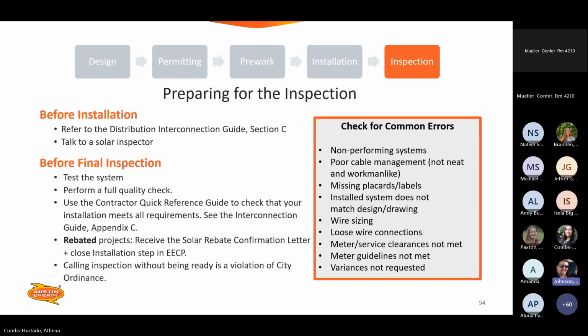Wire sizing, there are times we see too small of wires. We do have the interconnection guide, the DIG, that does tell us what size wires minimum, and same thing with the design criteria manual, what size wires minimum through any meter enclosure, what size grounding conductor through any enclosure. Loose wire connections or wires not being fully terminated in their terminal, so wire threads fraying out everywhere. Meter service clearances not met, so we talked about that earlier. Next to a gas regulator, too high, too low, something obstructing the clearance.